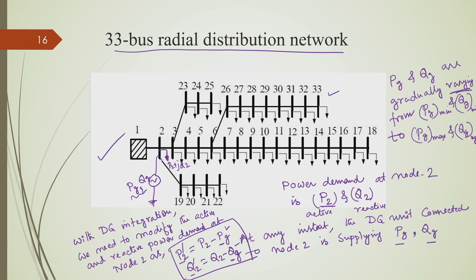PG max is here considered to be 8 megawatts. So by varying PG, the active power that the DG unit supplies, from a minimum value to a maximum value, we performed this forward-backward sweep load flow and computed the network loss. This is not the loss of an individual line, it is the overall network loss. If you recall, for the 33 node system without DG, the power loss was around 202 kilowatts.